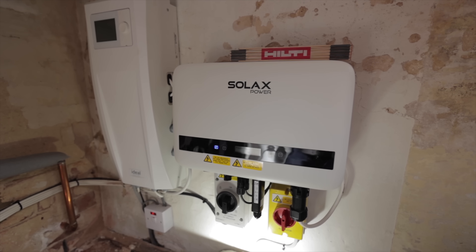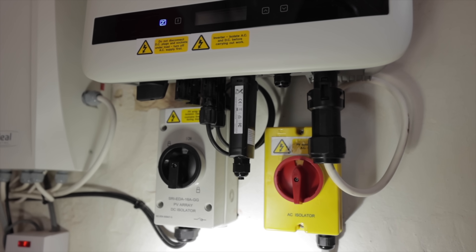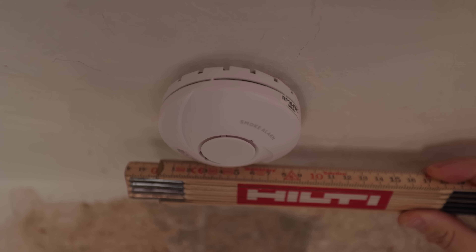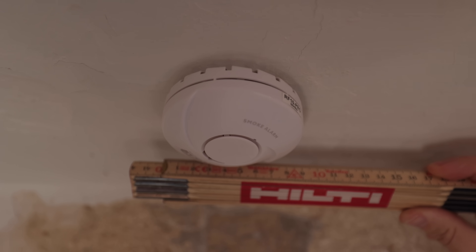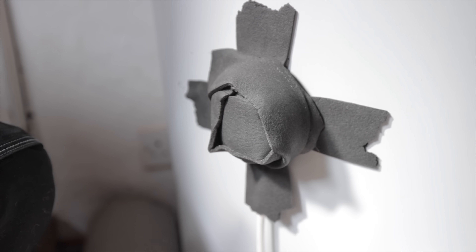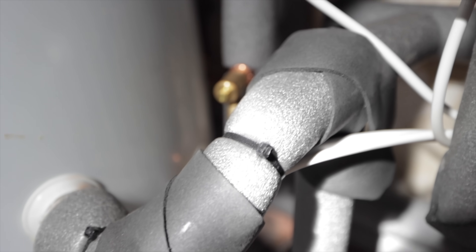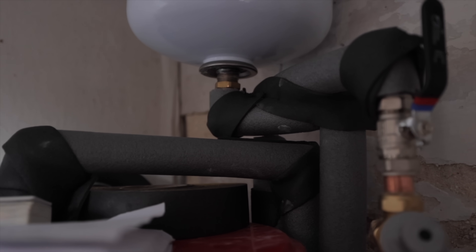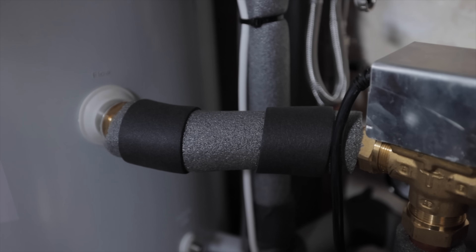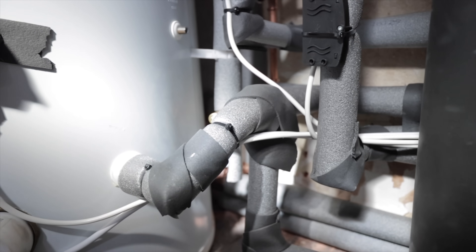There's a surprisingly small smoke alarm — shockingly small, though it does work. The pipe lagging on the heat pump installation looks like it's just been chucked in — more like a band-aid wrapped around the pipes than properly lagged pipework. A good heating engineer should be as OCD about their pipes and lagging as electricians are about their cables.